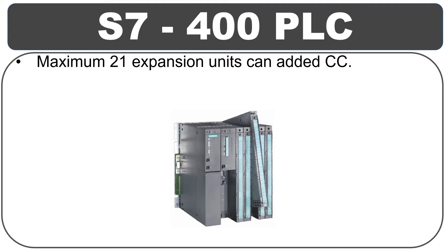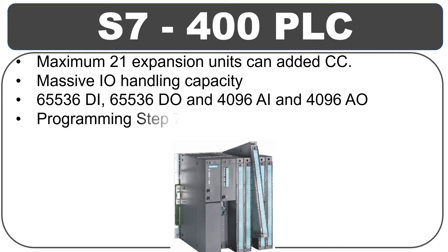The S7-400 has massive I/O handling capacity: 65,536 DI, 65,536 DO, and 4,096 AI and 4,096 AO. The S7-400 PLC can be programmed using Step 7 Basic and TIA Portal. Various communication interfaces are available in this PLC, including MPI, DP Master, Profibus, and Profinet.